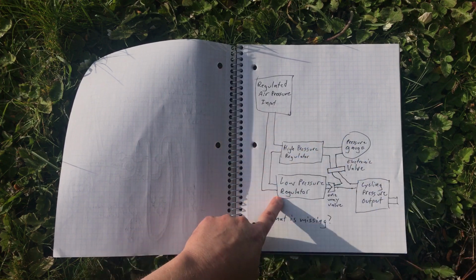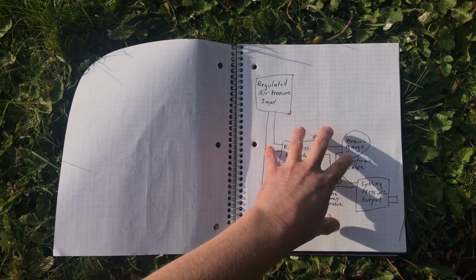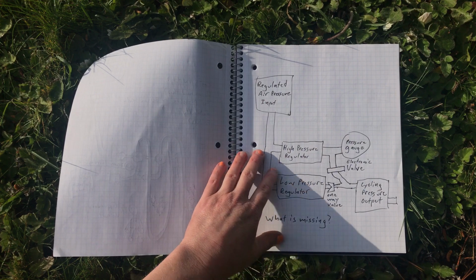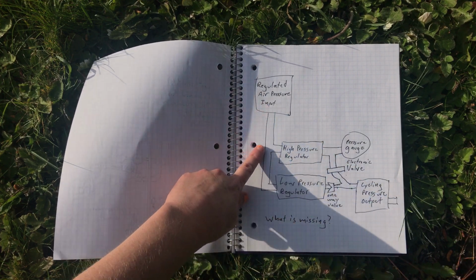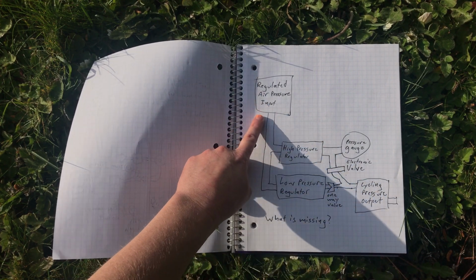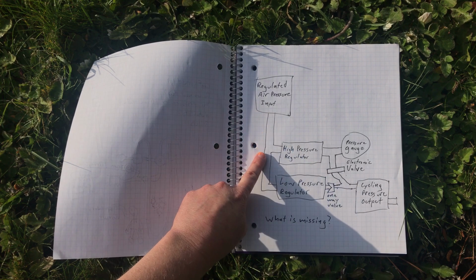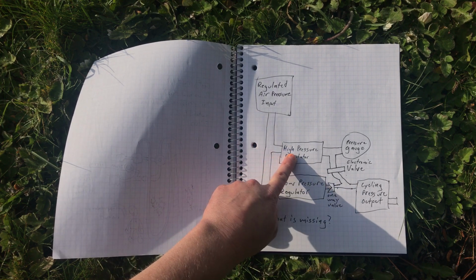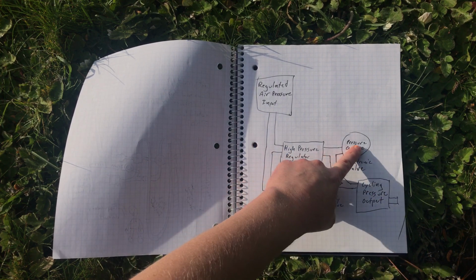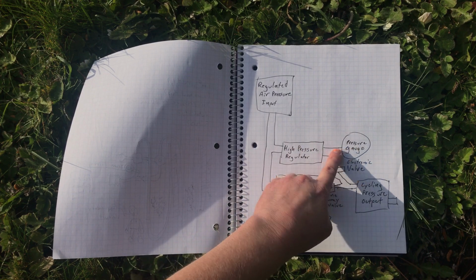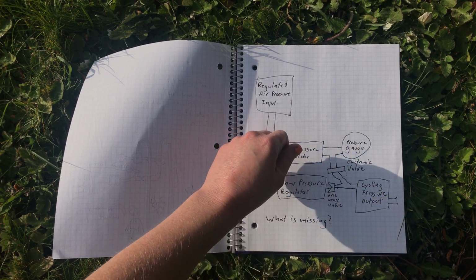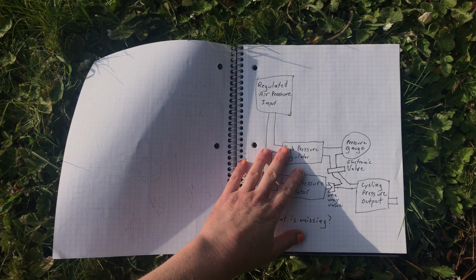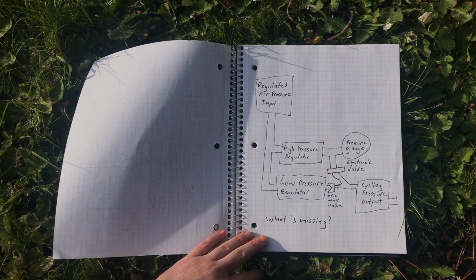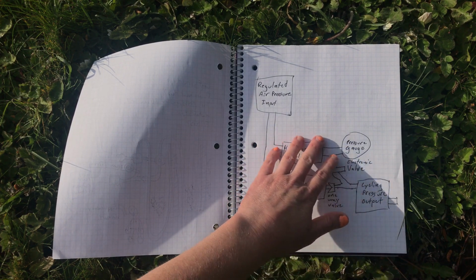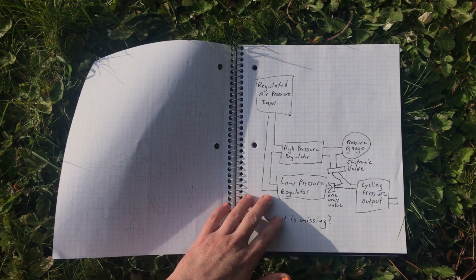Now, I'm imagining that this would all be in a single device, a single manifold. What you would have is a regulated pressure input that's slightly above the maximum that you would want. You feed into a high pressure regulator. You have some kind of pressure gauge. So this would be a valve or a mechanical thing that the operator would adjust for the desired high pressure that you want.